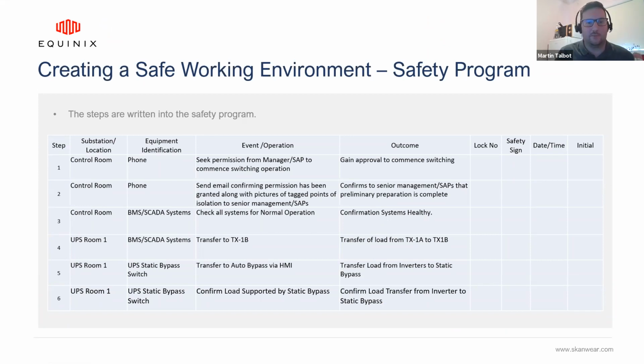And we put that inside of a safety program. Also inside this safety program, we want to include the things that Marcin was talking about: incident energy switches or reduced energy switches, however you want to term them. We want to turn them on at the right time at the beginning of the process, so that when we're switching, we keep incident energy low. But also, just as important, we want to turn them off again when the process is complete, because if they're left in the on position, our protection system is no longer selective after the maintenance is complete.